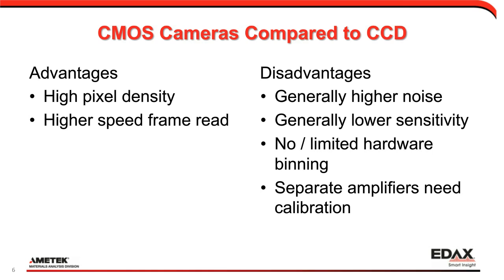CMOS cameras have no or very limited hardware binning. CCDs can bin up to 16×16, combining 256 pixels and reading them at once, but CMOS cameras typically cannot approach that. Additionally, because each CMOS pixel has its own amplifier, subtle intensity variations across the field of view can occur if those amplifiers are not well-matched. Manufacturers are working on calibration routines to address this, but it is something to be aware of currently — it is not a concern with CCD cameras.